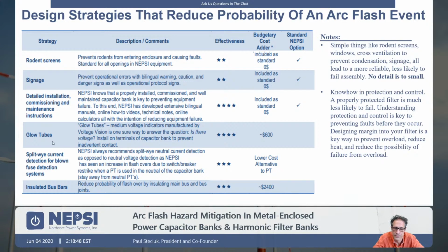Glow tubes. If you think about glow tubes, it's a device that sits on a bus bar. Okay, it comes at a cost of about $600. It tells you that the bus is energized. You put it in the incoming compartment. If you open the incoming compartment door and that thing is glowing red, no doubt you will not touch the bus bar. The bus bar is telling you, hey, I'm energized.